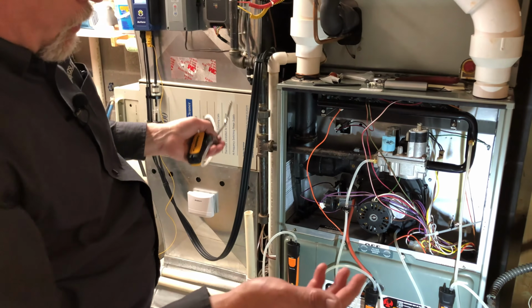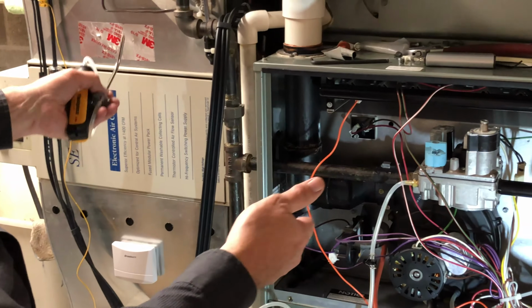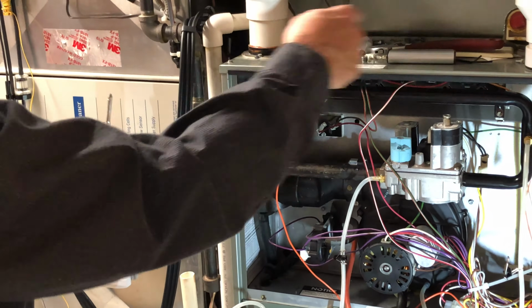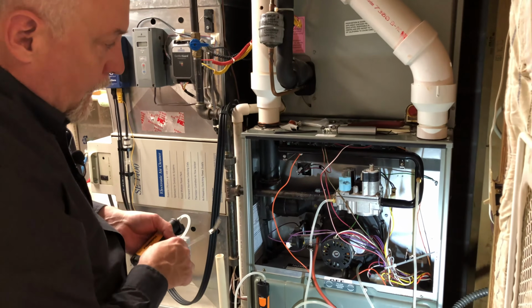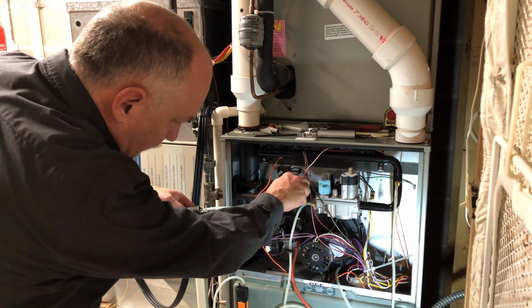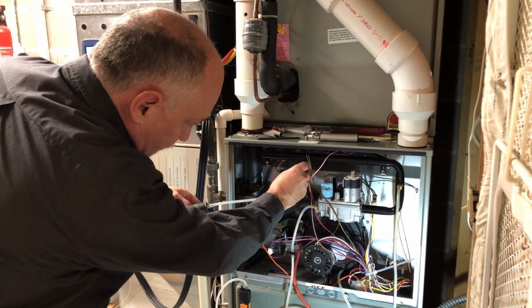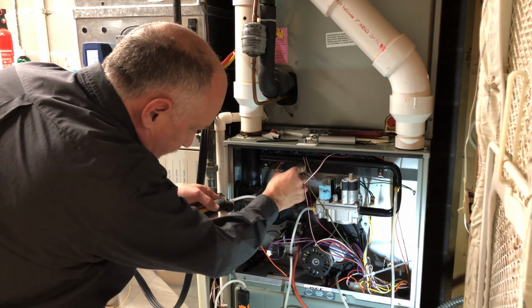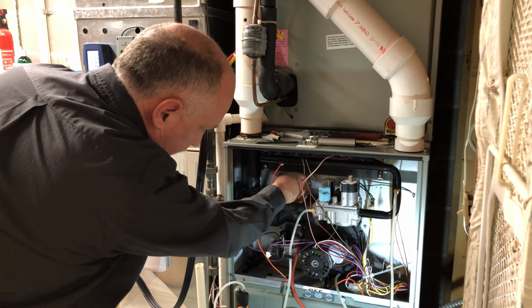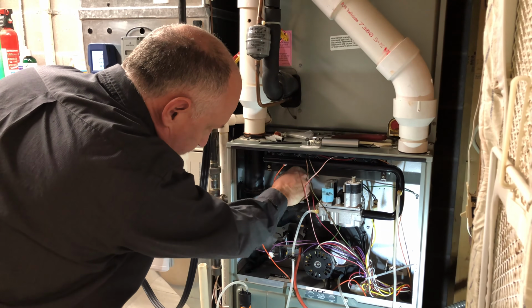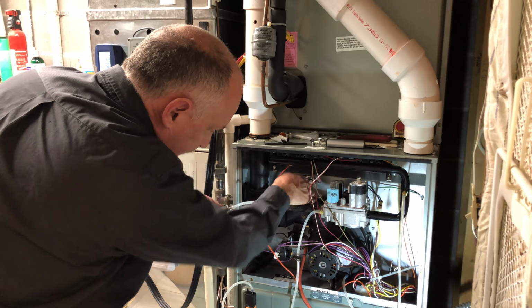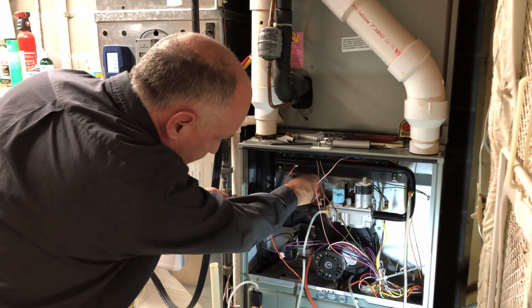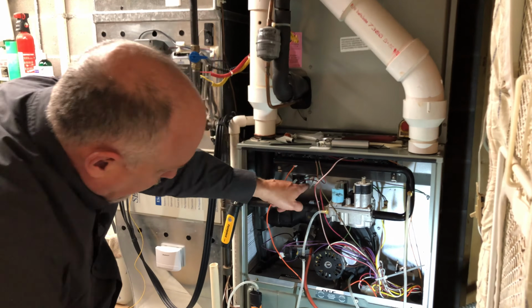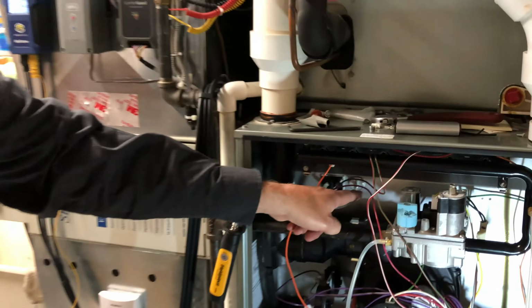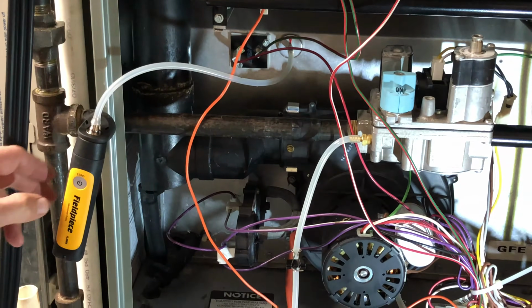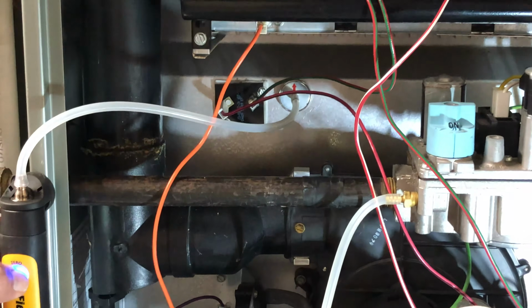And I've got a hole drilled here. This is a tricky situation where I've got no place I can drill a hole behind the coil. I needed a place to get in and make a static pressure reading, so I popped the hole here, and this will get me in near the heat exchanger. I just position that probe so I get it out of the path of the heat exchanger. You can see that arrow's pointed up, which means that it's in line with flow. Okay, so now I'm measuring my true supply air static.